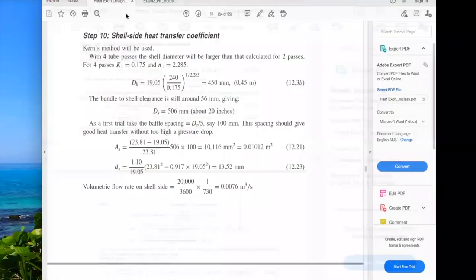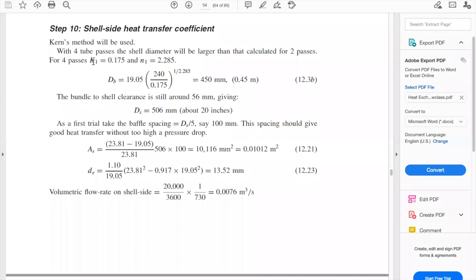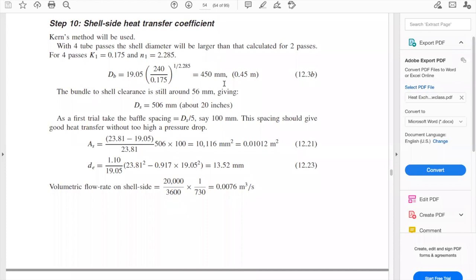With the new bundle diameter for four passes, we again read the shell clearance from Figure 12.10, getting approximately 56 mm, giving a new shell inside diameter of 506 mm. For the first baffle spacing trial, we use shell diameter divided by 5, which gives approximately 100 mm. This spacing should provide good heat transfer without excessive pressure drop.